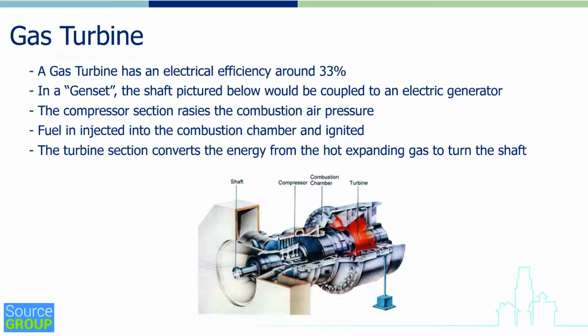Fuel is then injected into the combustion chamber and ignited. In order to inject the fuel into the combustion chamber, it must overcome the pressure of the combustion air, which at this point is 147, 150 pounds thereabouts. The gas pressure of the fuel has to be higher than that of the combustion section in order to get the fuel into the combustion section. The combustors in the turbine are sometimes referred to as combustion baskets or burner baskets. The turbine section converts the energy from the hot expanding gas in order to turn the shaft.